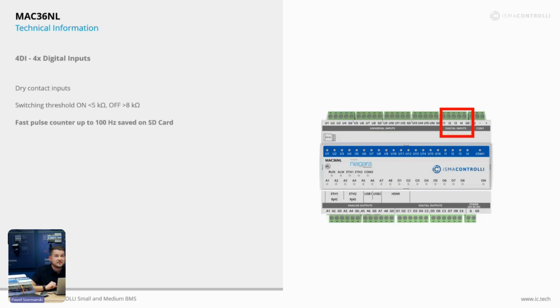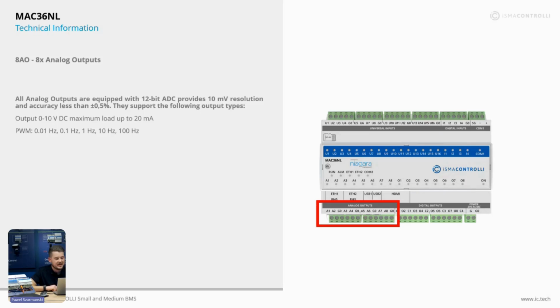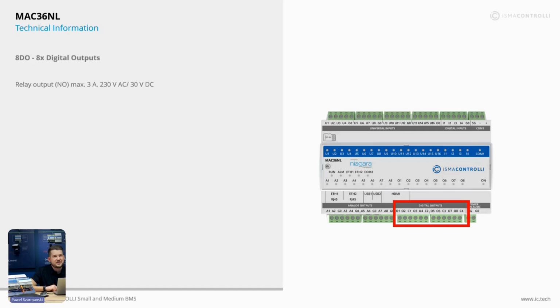Then we have 4 digital inputs that work with a fast pulse counter and can save up to 100 pulses directly to EEPROM memory and safely store it on the SD card, so you can also use it for metering purposes. There are 8 analog outputs at 0 to 10 volts, and 8 digital relay outputs with up to 3 ampere load.